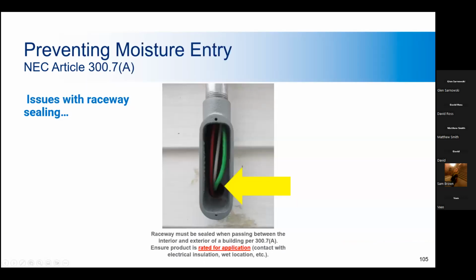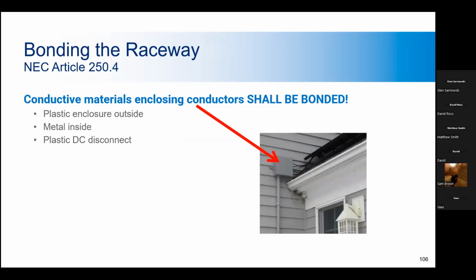Here we have an example of conduit passing from the outside to the inside of a building, and it's not sealed. There's a potential for condensation buildup where the warm building air meets the cooler outside air, or vice versa. And once the condensation forms, it has no place to go but down the conduit into the panel that this enters into. And there could be live circuits, and water and electricity is not a good combination. So you want to avoid that. This is a violation of the electrical code and the energy code, since there's an energy component to it.